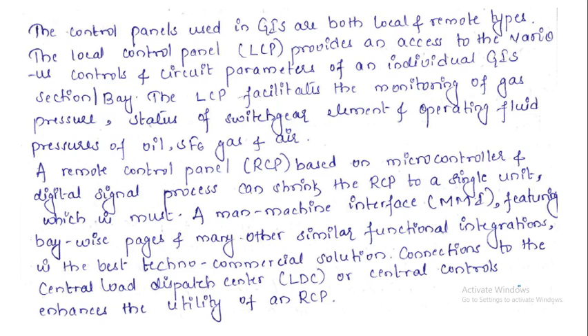Connections to the central load dispatch centers or the central controls enhance the utility of an RCP. So to connect to the load dispatch center or the central control, we need to do the communication between the substation as well as the control center. In order to do this communication, various equipment or machines are used, such as an MMI, man-machine interface, bay-wise pages, or similar functional devices.